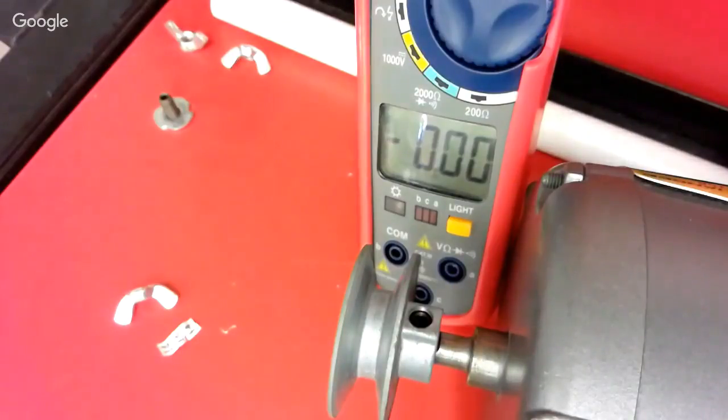So if you see somebody pull out a clamp-on probe that only works on AC and clamp it around an extension cord and say, I don't know, it's not working, they don't know what to do. Now you do. You've got to check each individual wire. If you check them all, it's going to cancel itself out.